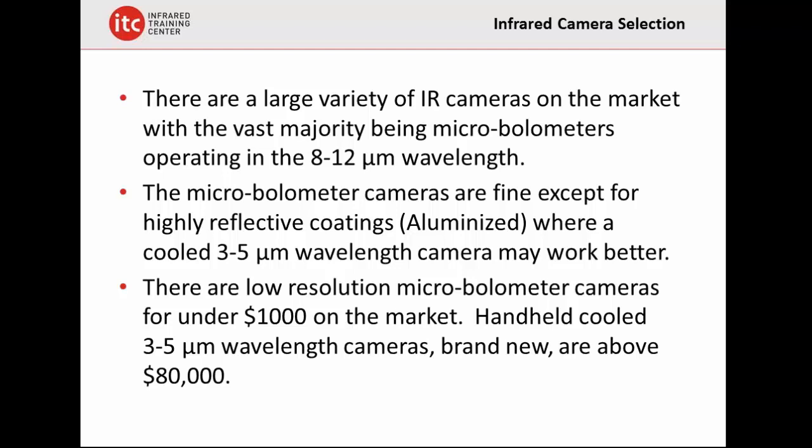But in the early days of doing infrared thermography, we used to use the AGA 782 cameras. I believe they had a MERCAD, mercury cadmium telluride detector that operated in the midwave. I might be wrong on that, but they were 3 to 5 micrometer cameras, and on the aluminized coatings we got great images off of them. So that's unfortunate, that today's technology, the lightweight, inexpensive, relatively easy to use cameras, fail on those aluminized coatings.